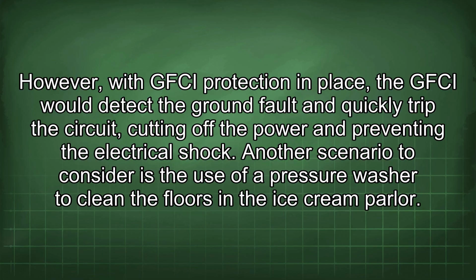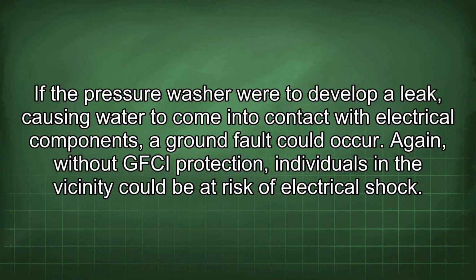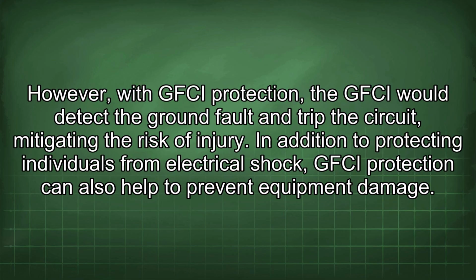Another scenario to consider is the use of a pressure washer to clean the floors in the ice cream parlor. If the pressure washer were to develop a leak, causing water to come into contact with electrical components, a ground fault could occur. Again, without GFCI protection, individuals in the vicinity could be at risk of electrical shock. However, with GFCI protection, the GFCI would detect the ground fault and trip the circuit, mitigating the risk of injury.